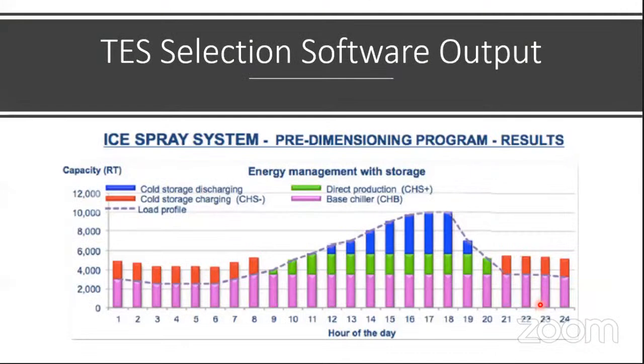So this is a kind of output that is generated. This is a graph. It's a 24-hour load profile that is segregated between three components: your base load chiller, then your brine chiller, and then thermal energy storage cooling, and these are your charging hours. So all this is generated.